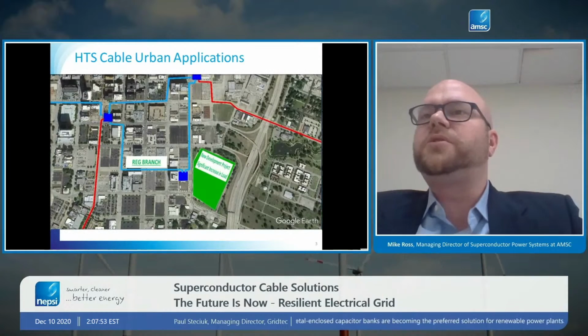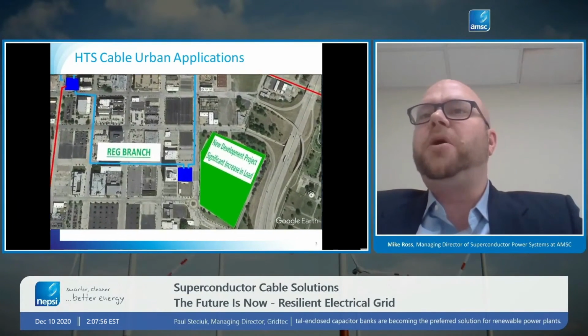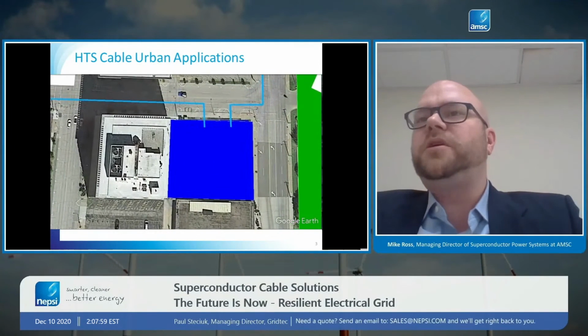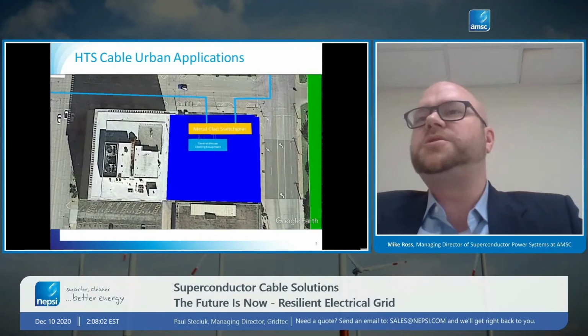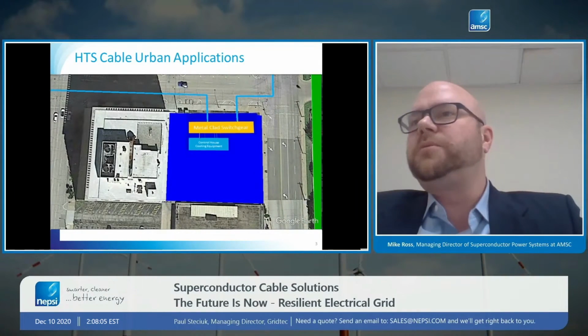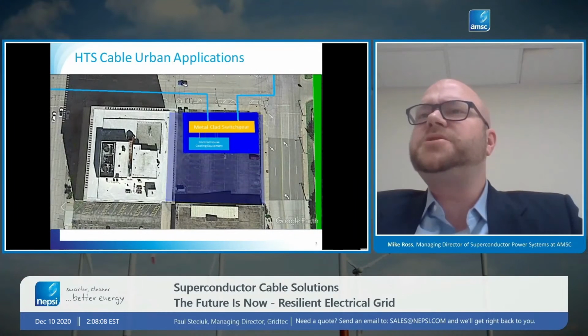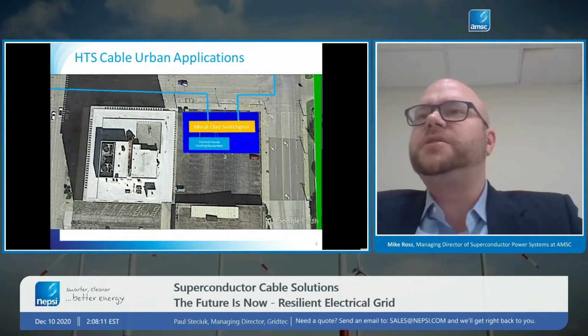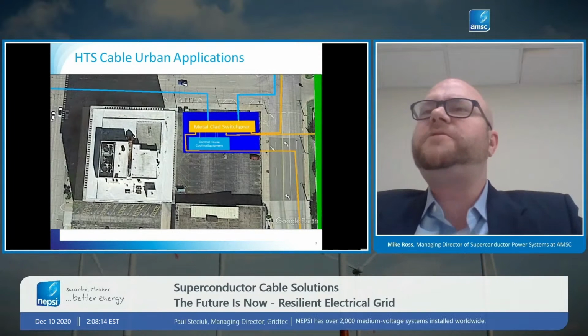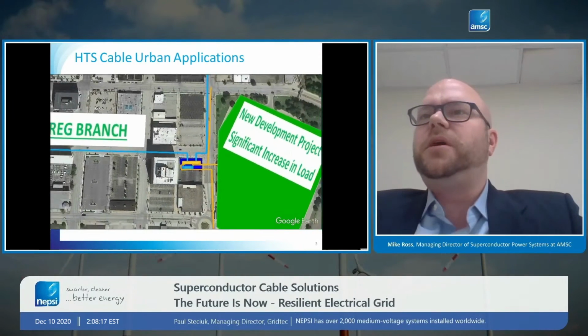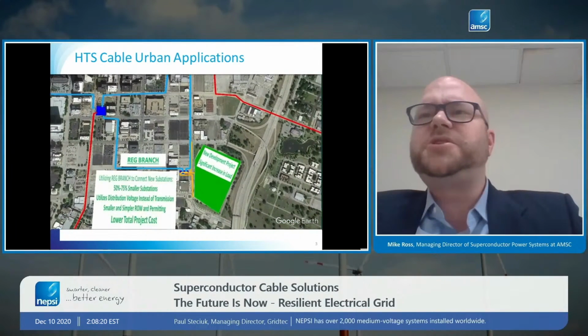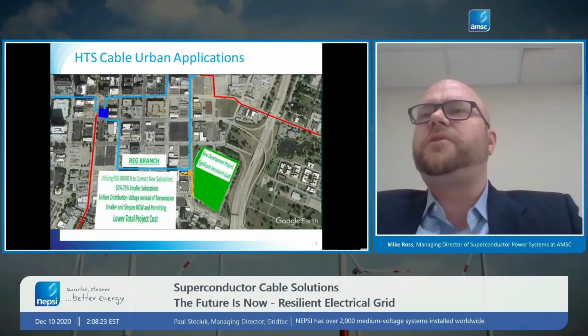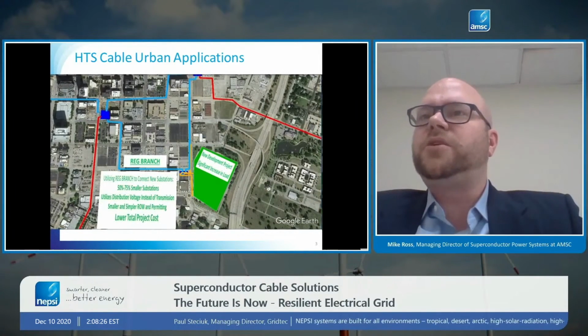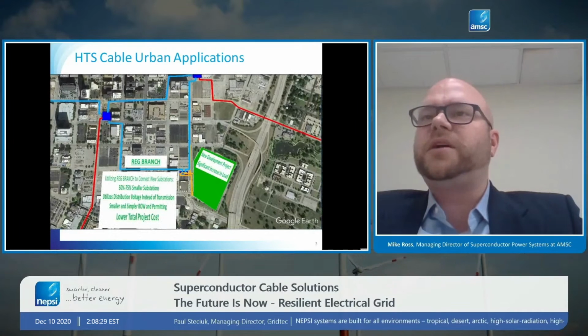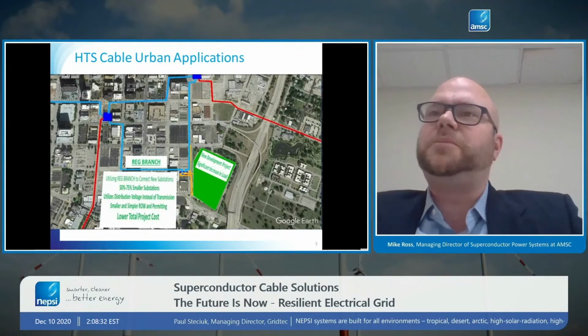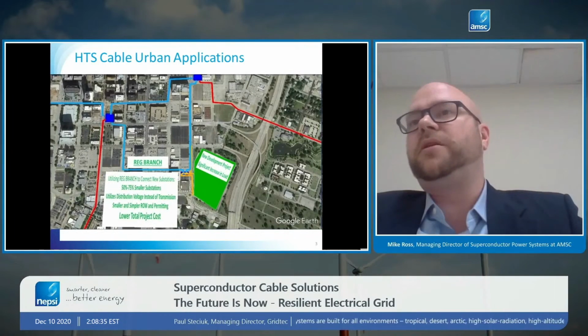So one alternative that this technology can bring is to be able to bring bulk power through superconductor cables to these new substations at distribution voltages. So at lower voltages, we're bringing power to the new substation, and as a result, you don't need to have as big of a substation. In fact, the substation can be about 25% the size of a typical full substation, which is much easier to site and far less expensive, far easier to permit, and that in turn creates lower cost overall projects in those scenarios where you do indeed have to build new substations in urban areas.